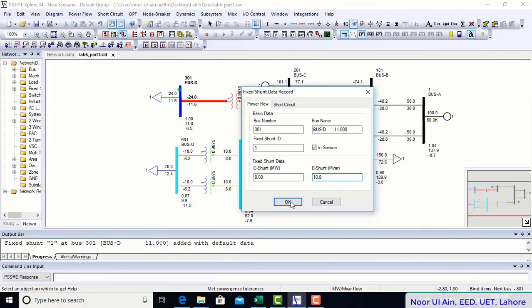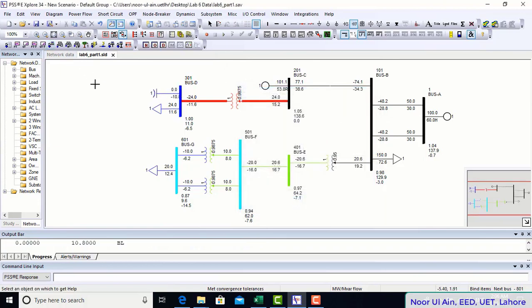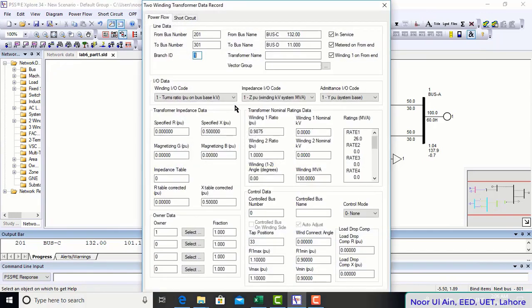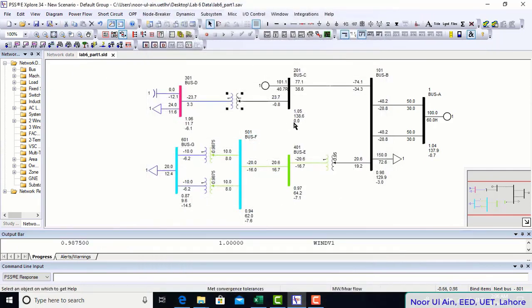Right, which is a multiple of 1.2 and close to 11.6. And let's see the system response. So now I'm having over voltage at this bus. Okay, I can basically revert the tap setting of this transformer in order to reduce the voltage at this bus, and let's see. Okay, now it's fine.